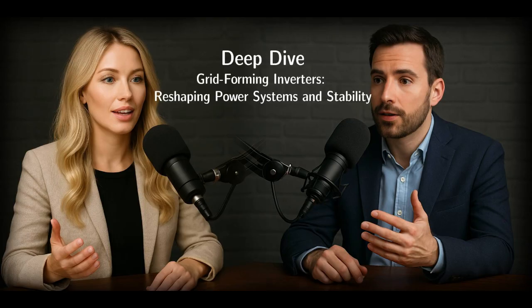Absolutely. This is a critical area for adaptation. Protection systems have traditionally relied on the high fault current from synchronous generators, typically 5 to 10 times the rated current, or per unit, to detect and isolate faults quickly. Grid-forming inverters provide much lower fault current, typically in that 1.2 to 2.0 per unit range. It's programmable, and they can sustain it for longer, but the initial magnitude is significantly lower. So if you're a protection engineer, how does that lower, more controlled fault current mess with your traditional schemes?